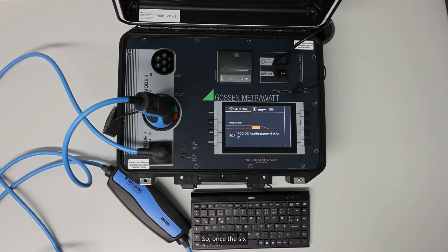So once the 6 milliamps have been tested, we still have the functional test to do. Functional testing is very important. We know there are different statuses in the charging process. There is status A, which means plugged in. Here we have the 12 volts. There is a status B, which means it is locked. This means you cannot pull out the charging cable during the charging process anymore. In this case, that would be plus 9 volts, minus 12 volts, and 1 kilohertz.